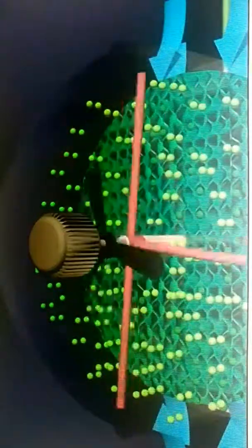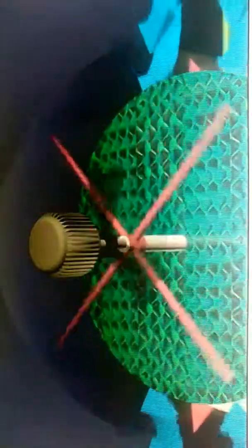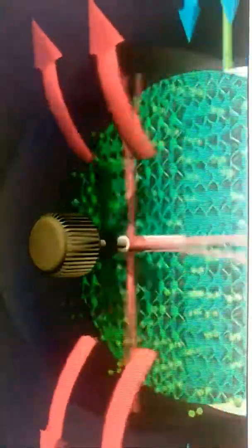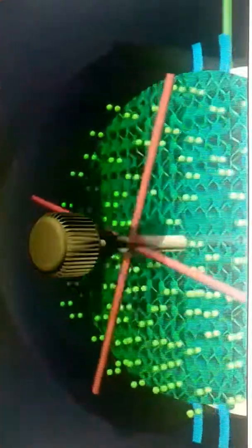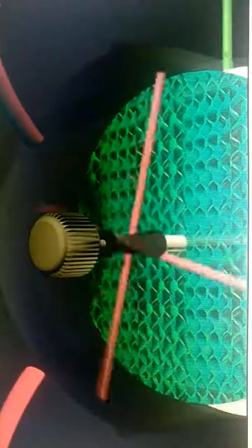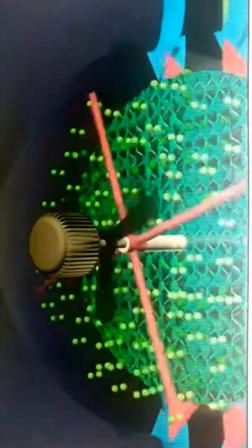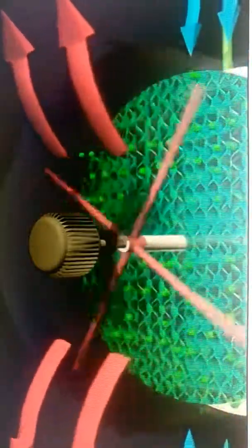Water will gush down through the fins to reduce the speed of the water going down. This delays the time so the heat can be absorbed more effectively by the surrounding air passing through the fins. Air through the fins is forced by a rotating fan on the sprinkler blade, rotated by the motor. This fan rotates with its gusts upward. This causes the air to move from the bottom to the top of the cooling tower, opposite to the flow of the condenser water.